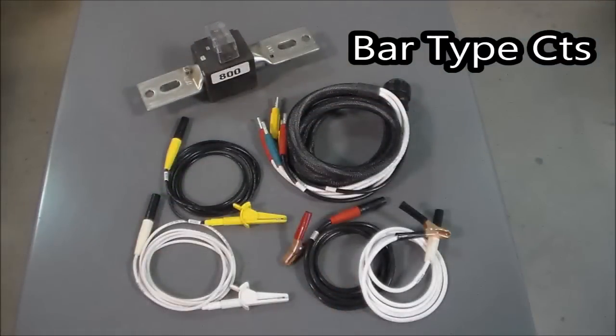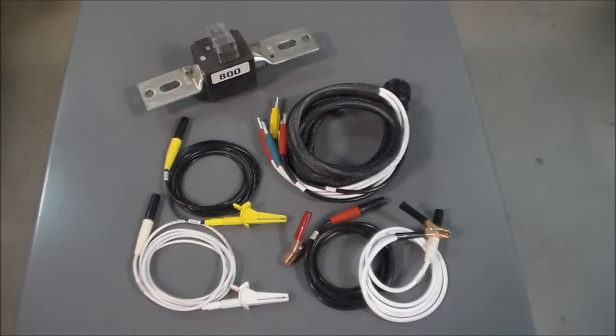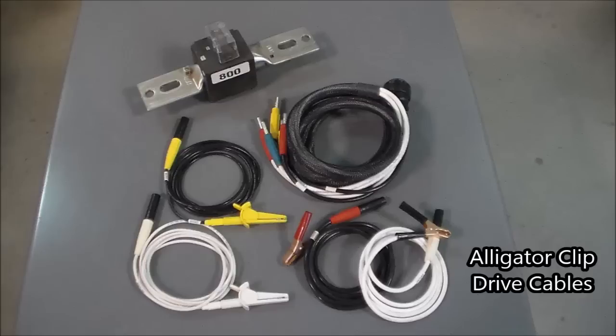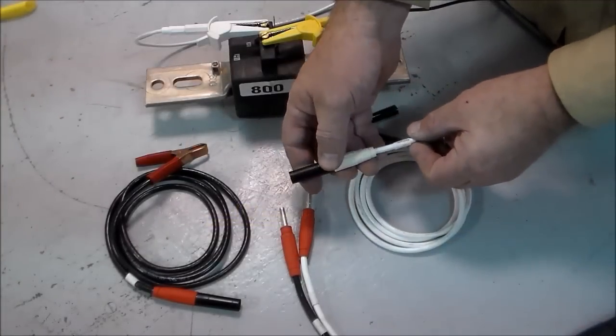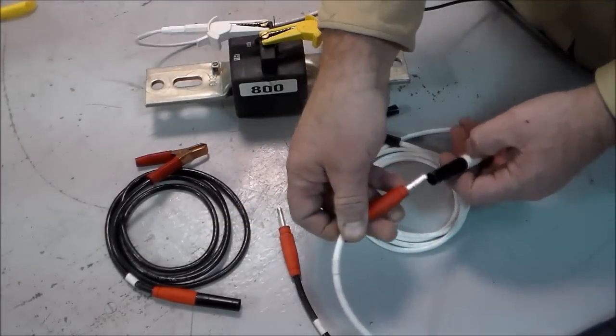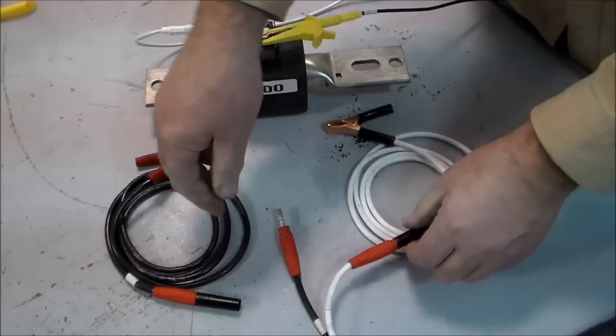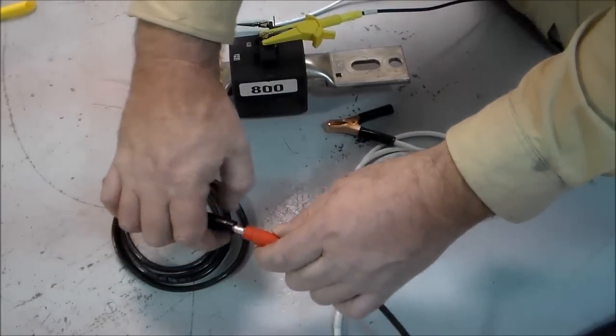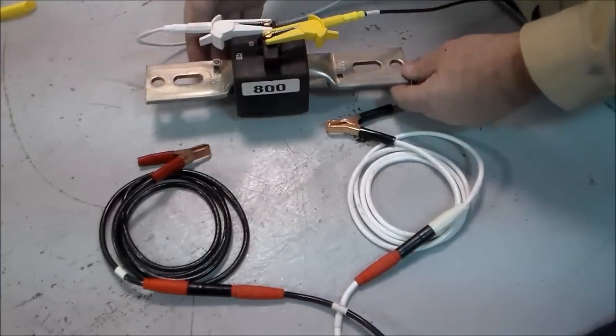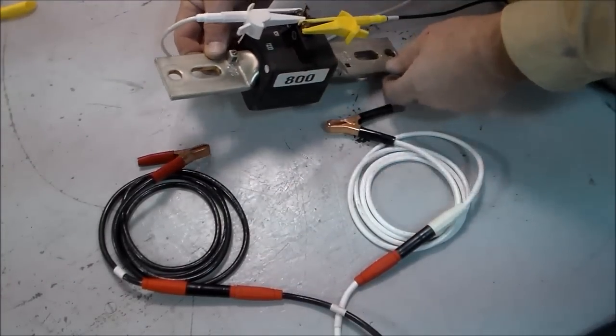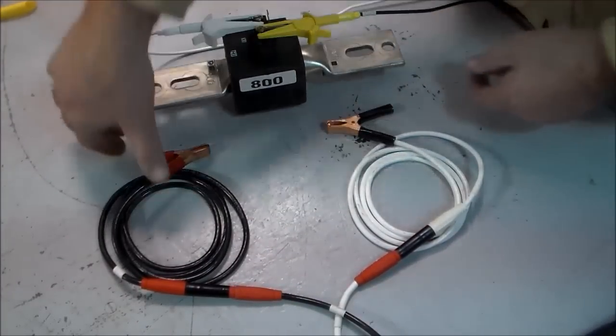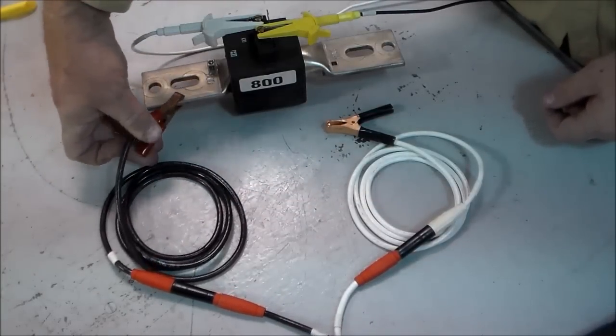Now let's look at bar type CTs. This test will work with any windowless CT, and it's basically the same test, we're just using a different drive cable. They're shown here on the bottom right, and the only difference is they have alligator clips instead of BNC connectors. Your leads will hook up the same as the window CT test. There's just a different drive cable. We're still observing the same polarity. The drive cable goes on the polarity side.